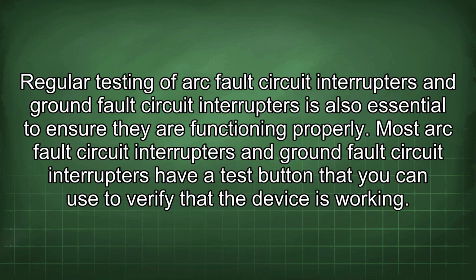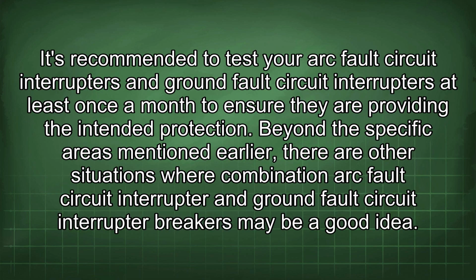Regular testing of arc fault circuit interrupters and ground fault circuit interrupters is also essential to ensure they are functioning properly. Most arc fault circuit interrupters and ground fault circuit interrupters have a test button that you can use to verify that the device is working. It's recommended to test your arc fault circuit interrupters and ground fault circuit interrupters at least once a month to ensure they are providing the intended protection.